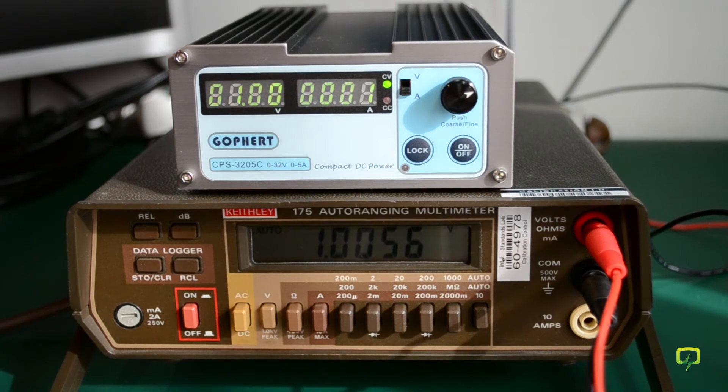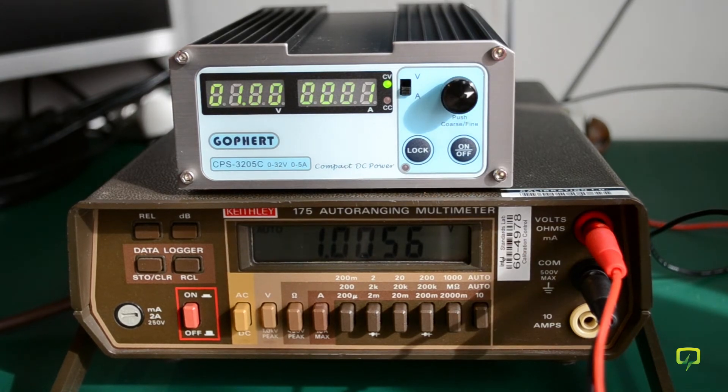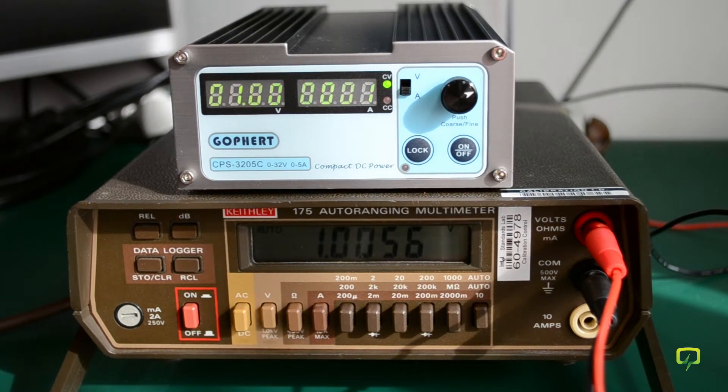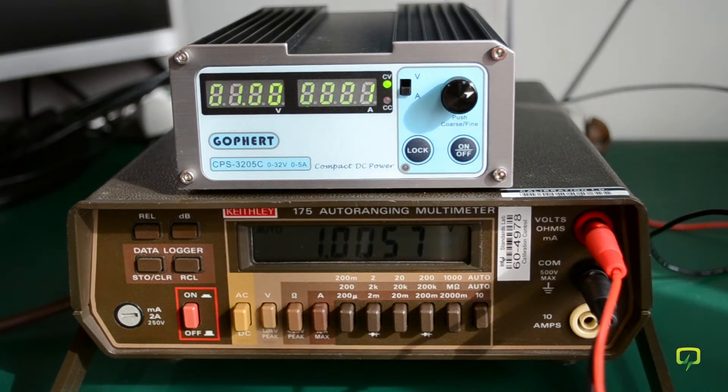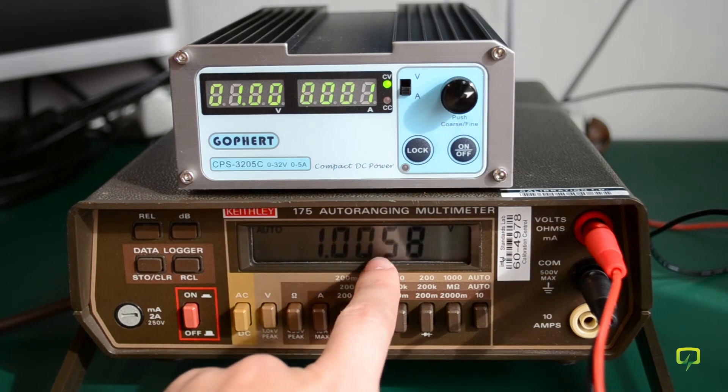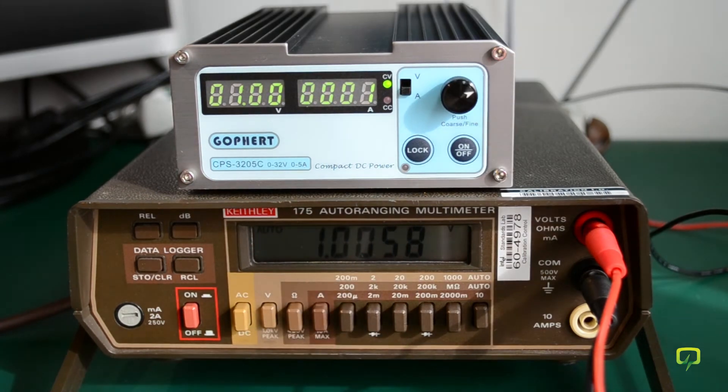Now you have to adjust the knob to set the output voltage to 1.005 volts. I'm not sure why they chose this exact value. I mean, you're basically adjusting for the 1 volt scale, so why they went for the 1.005 volt figure, I don't know. Maybe they take into account some internal circuitry. But as you can already see, the voltmeter on the power supply is quite accurate, and I can see 1.005 on the multimeter.